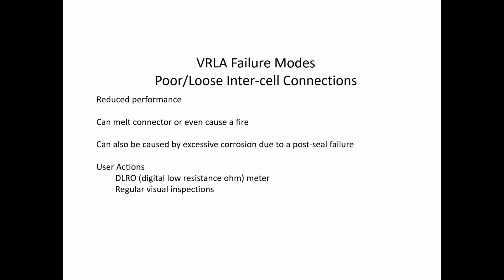I hate to say this isn't really a failure mode, but poor or loose connections are also important to monitor on the battery. I don't believe I've ever seen a battery connection loosen itself in the field. If we've seen poor or loose connections, it's from time of install, and no one ever caught it. It was a misconnection, it wasn't torqued down, and it just wasn't done. Connections can go bad if corrosion is allowed, if there's a post seal failure and corrosion forms around the post and gets between the mating surface of the connector and the post. But for the most part, the bad connections we see are from the install.